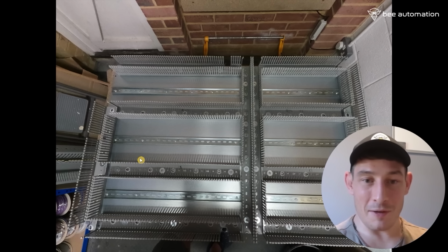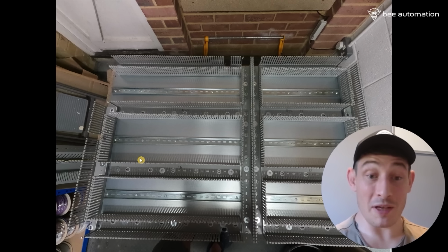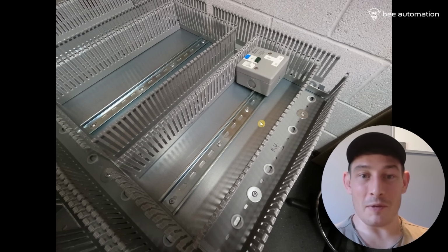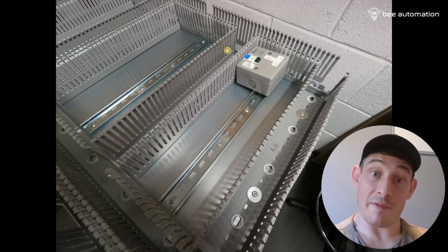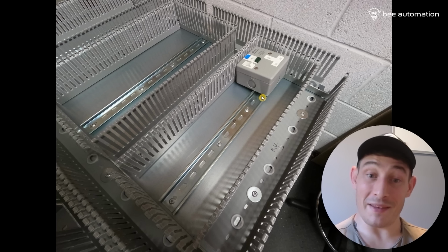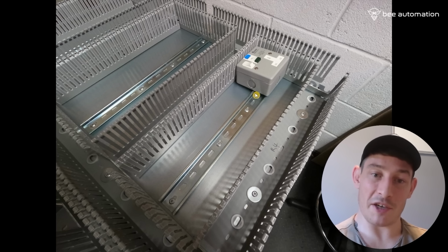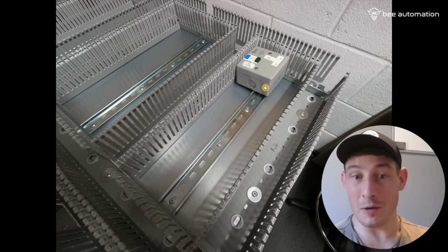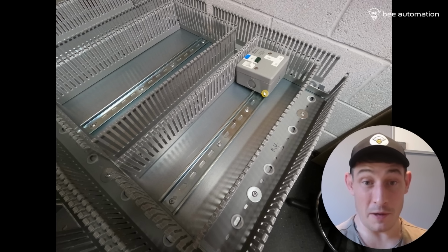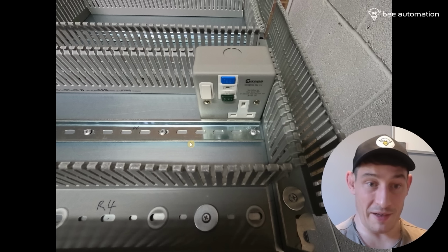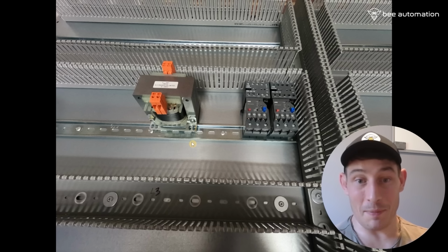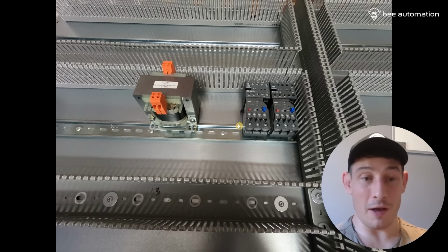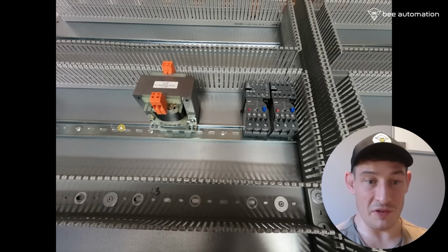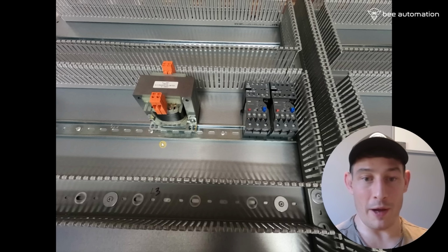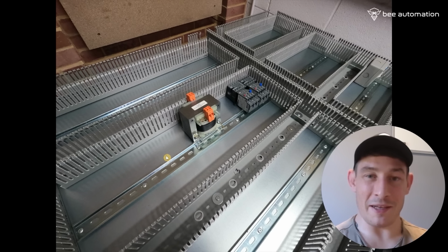Little mistake that I've made, and typical, I do this kind of thing most of the time. If you look at the drawing, we're actually meant to have a laptop socket, or just a socket in general here, but I've made the din rail go across that whole section when it should have been cut off here. So that's something that I need to rework. The din rail should have ended here. It's exactly the same thing with the contactors, overloads and the transformer - I've run the din rail all the way along. So yeah, a couple of things that needed correcting there.